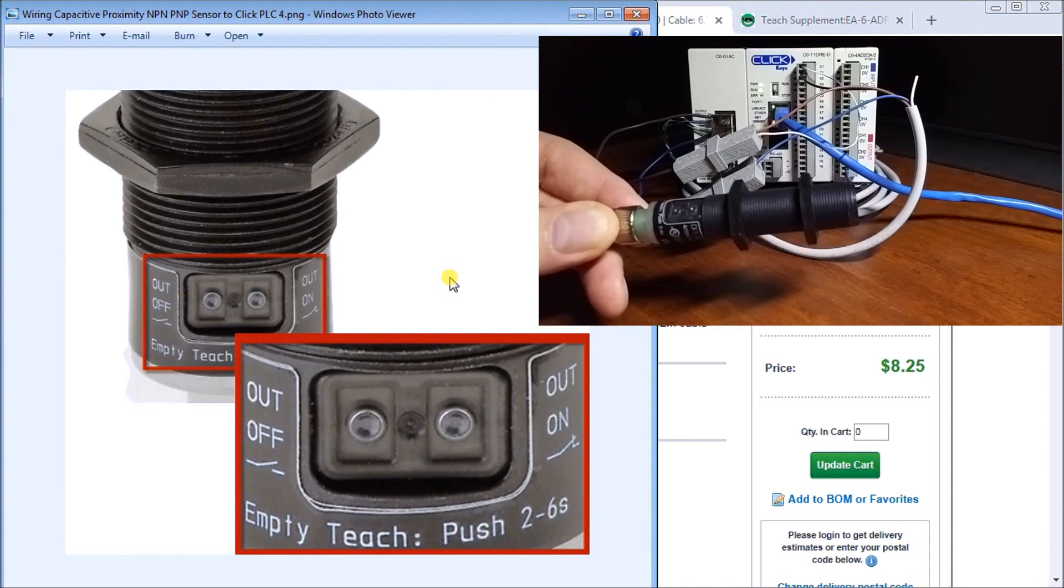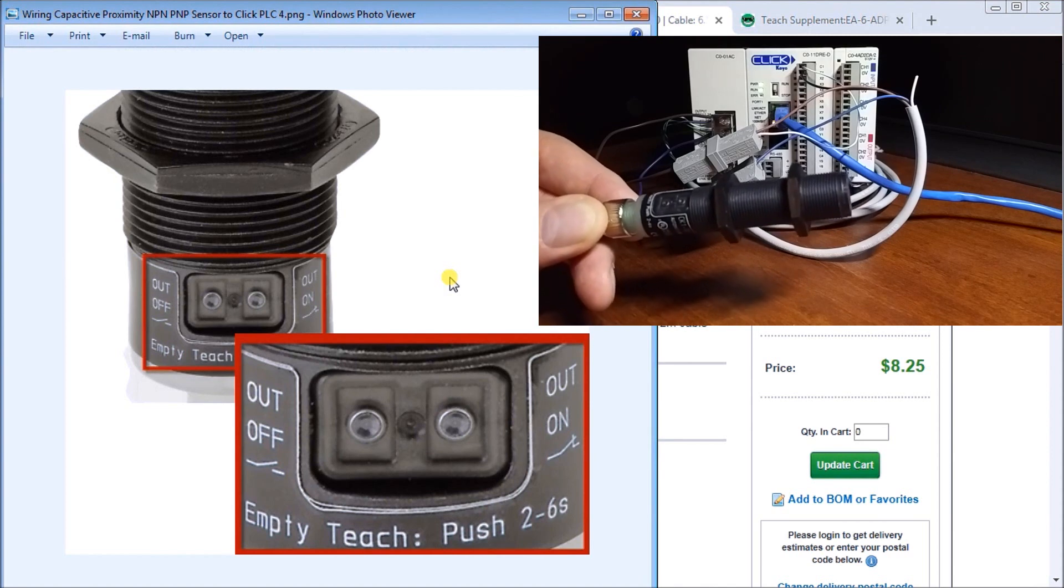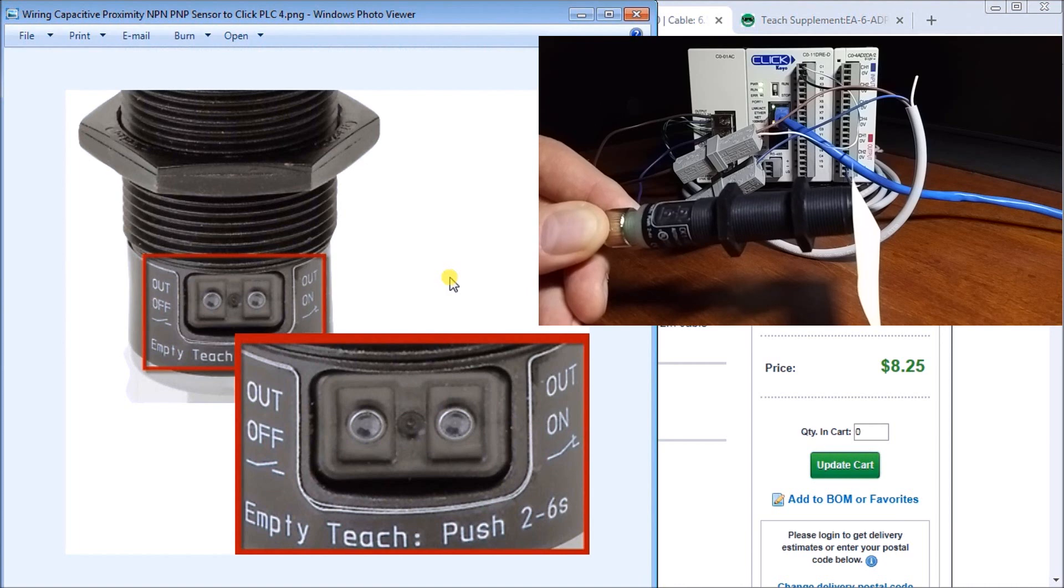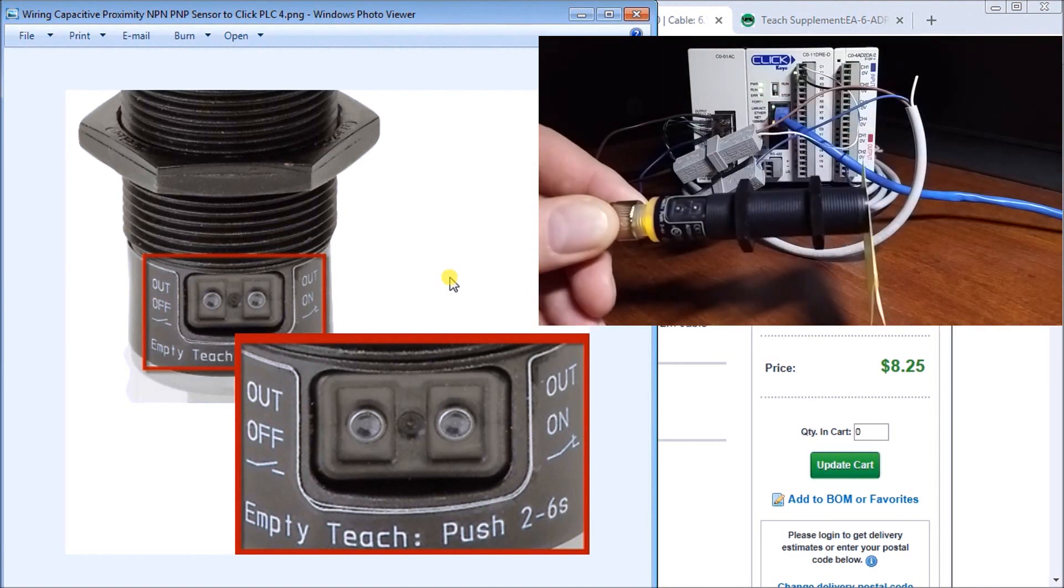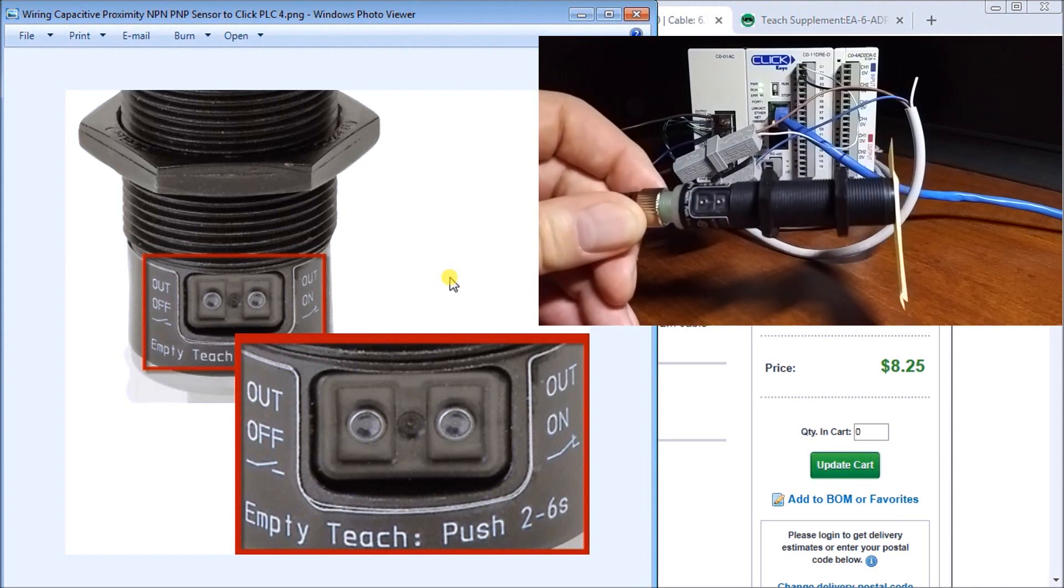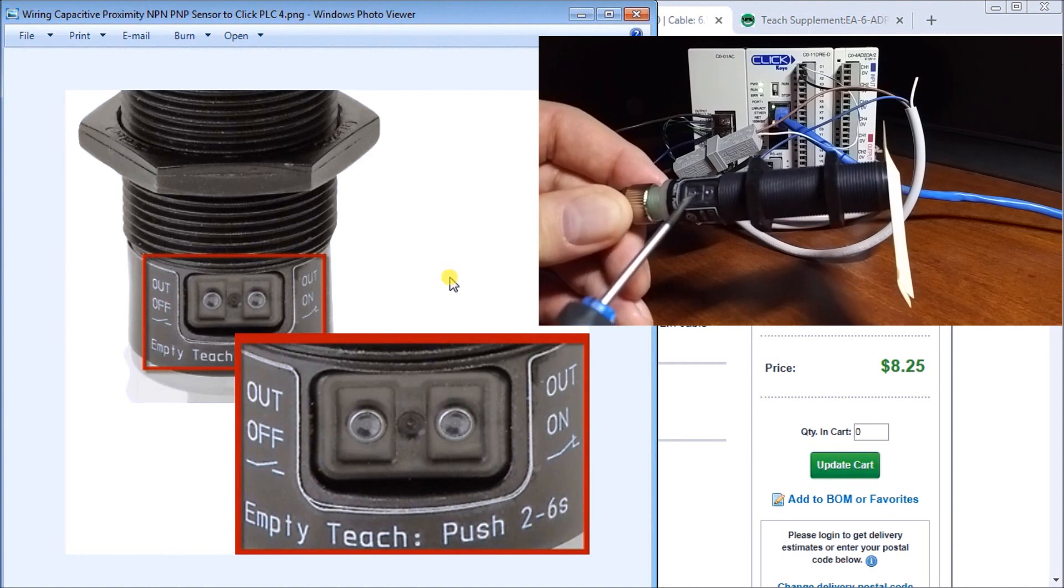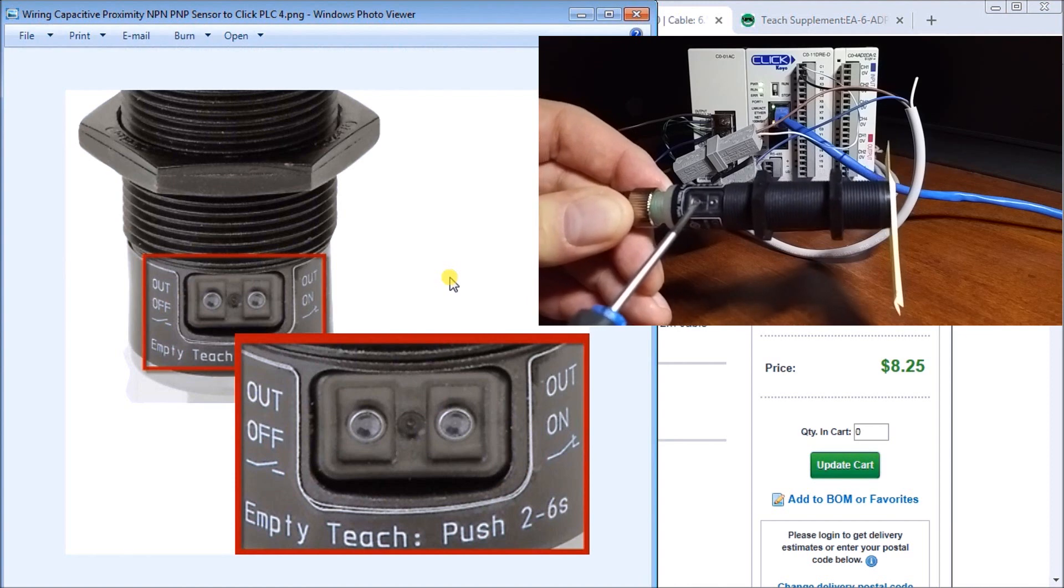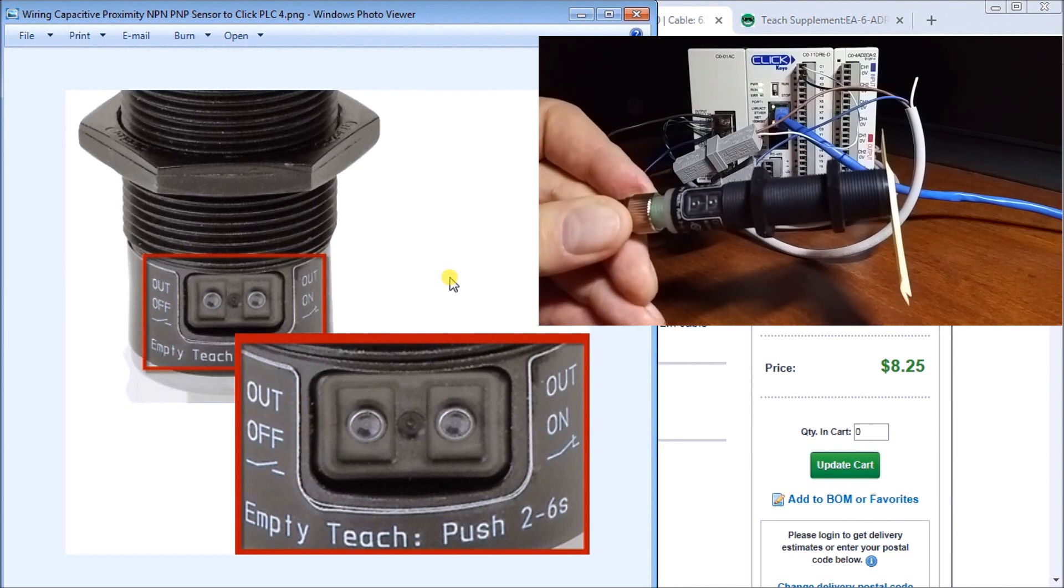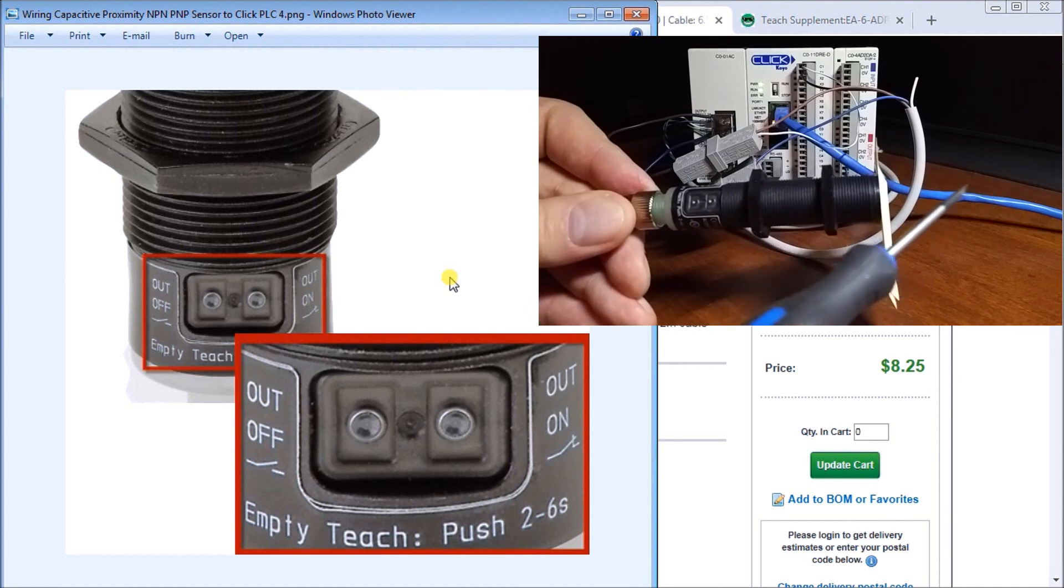Now over time what you'll see is that we will have dust and build up possibly on the end of the sensor and when that happens sometimes it will detect when we don't really want to detect. So we can zero that out again by hitting and holding our out off and this time here we will hold it for over six seconds. You'll see it flashes a little bit quicker and then we can let go and now we've tared it so that we now have our dust or whatever is on the sensor and we can still make it operate.